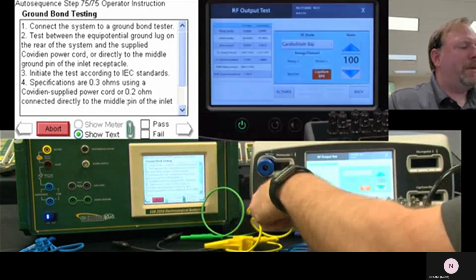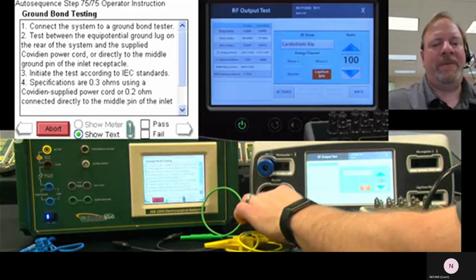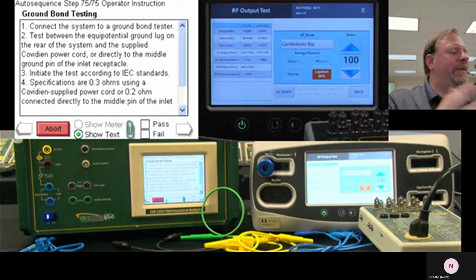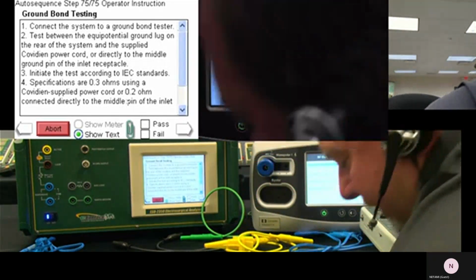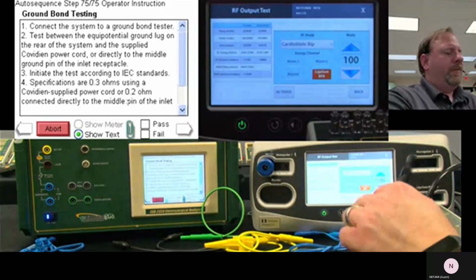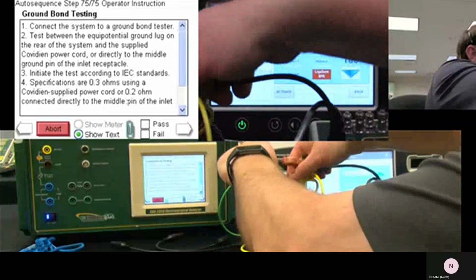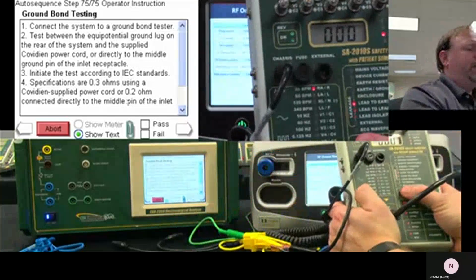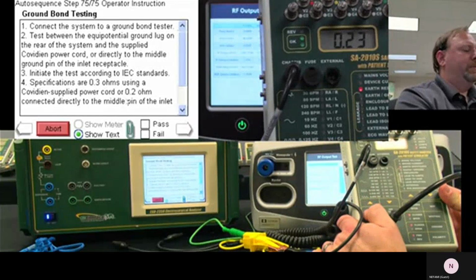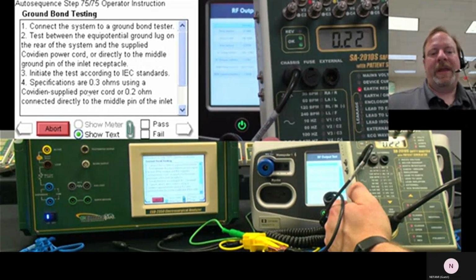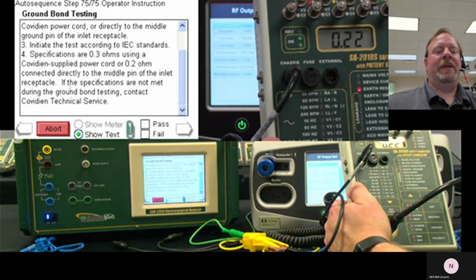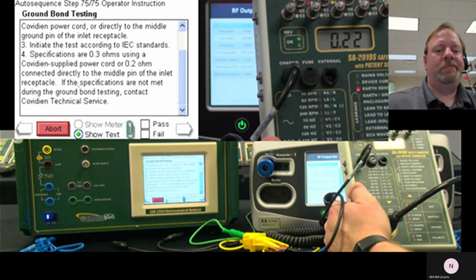Now, the ground bond testing in the service manual at the manufacturing facility, typically ground bond testing is done at 25 amps, and it can be fairly destructive. But the safety analyzer here can conveniently measure the earth resistance. So I'm going to connect this to our ground lug on the back. And we can measure earth resistance here: 0.22 ohms. Specifications are 0.3 ohms using a Covidien supplied power cord, or 0.2 ohms connected directly to the middle pin of the inlet receptacle on the back. So in this case, it's good, under 0.3.